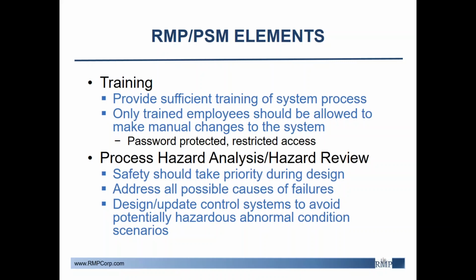Another element at play in this scenario is process hazard analysis. The refrigeration system included multiple evaporator units connected to a single control valve group, which can be a severe overpressurization hazard. Initially, this design reduced costs by reducing the number of valves that needed to be installed. However, ultimately, the damage caused by the hydraulic shock was much more costly and impacted many lives. It is imperative that safety take priority during the design process and throughout the process life cycle. Accurate and thorough process hazard analyses can help mitigate hazards and bring to light weak points in the system. Efficient PHAs can allow for the design of better safety systems and independent protection layers.